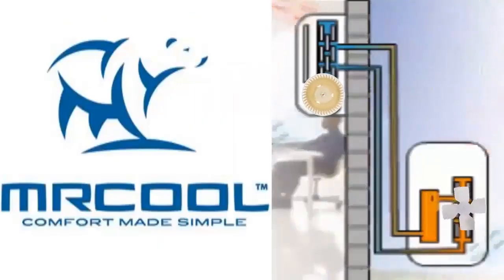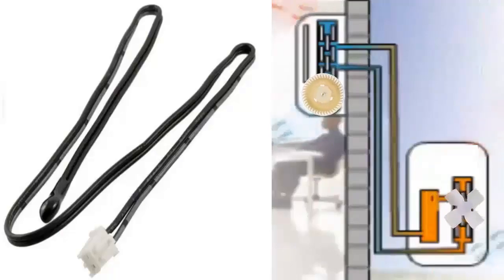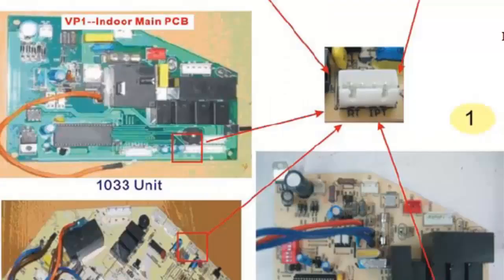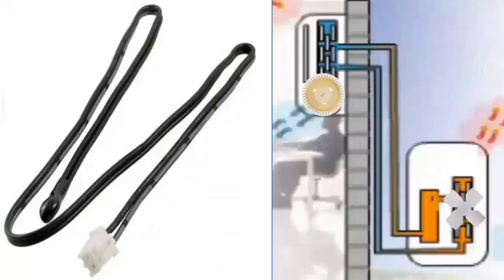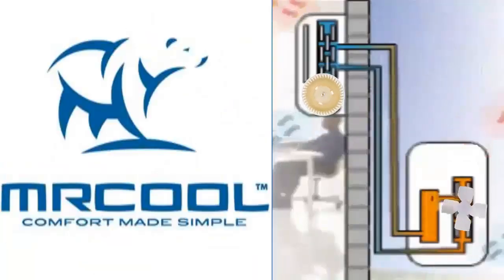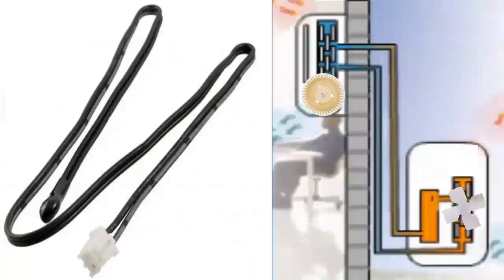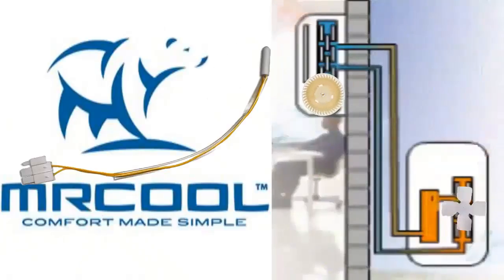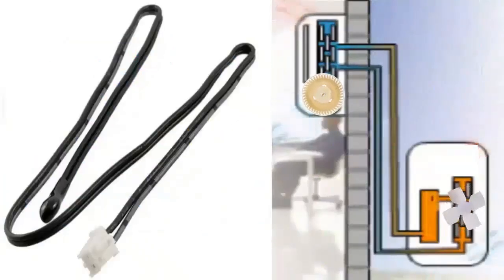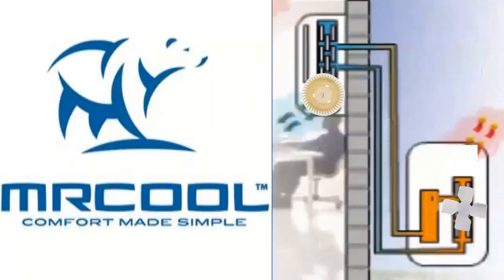7. If the problem persists, the issue is likely with the electronic controller associated with the temperature sensor. Conduct a visual inspection for anomalies, test suspicious electronic components, and measure the components near the sensor connector. 8. If you can't find the fault, first try replacing the sensor with another of the same value. If the problem persists, replace the unit's electronic control board where the affected sensor is connected.